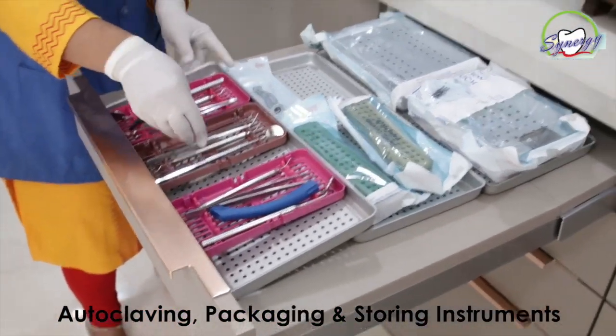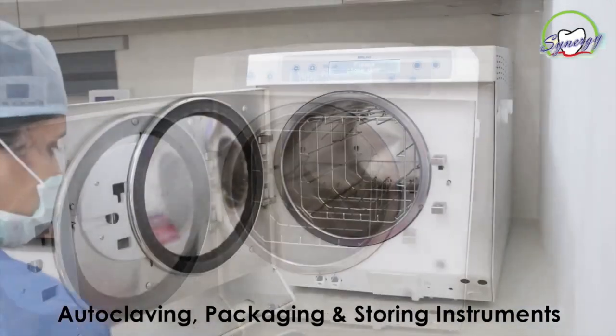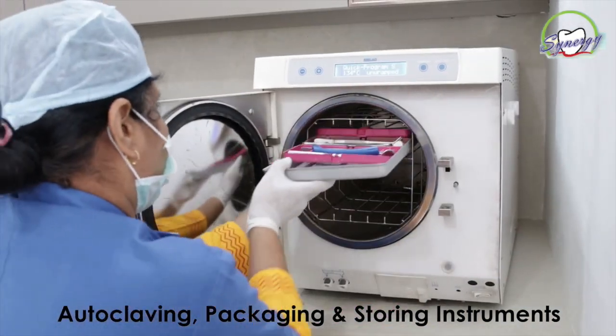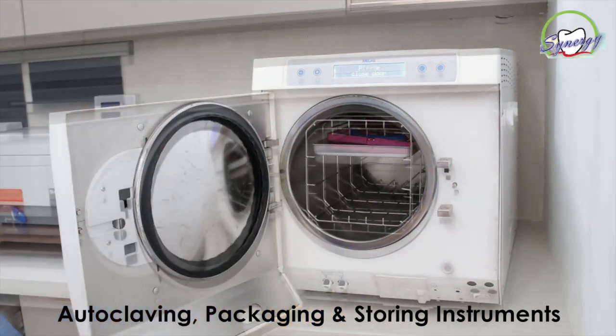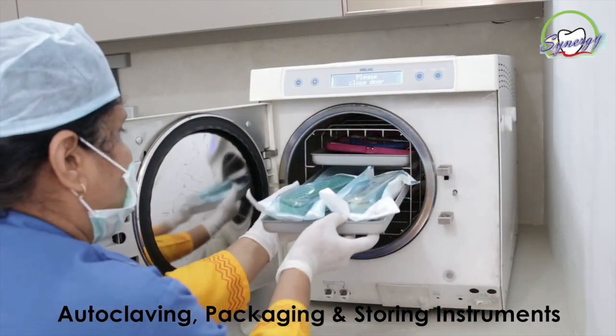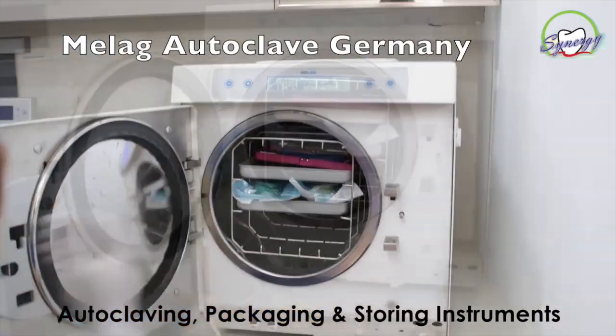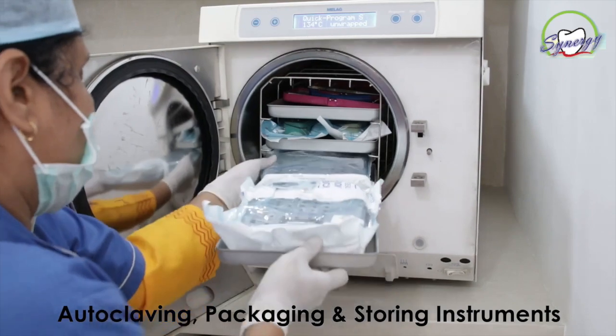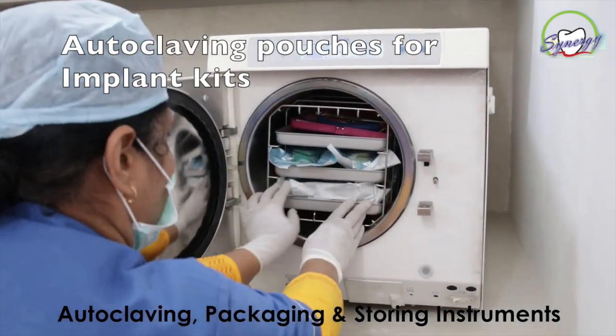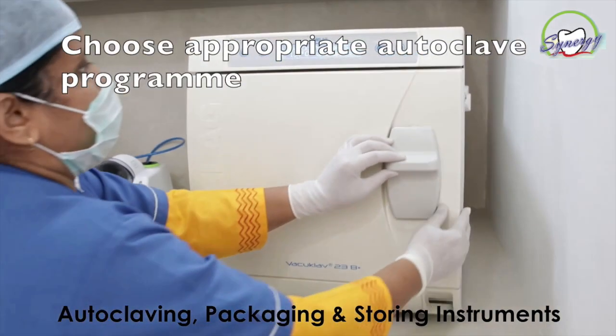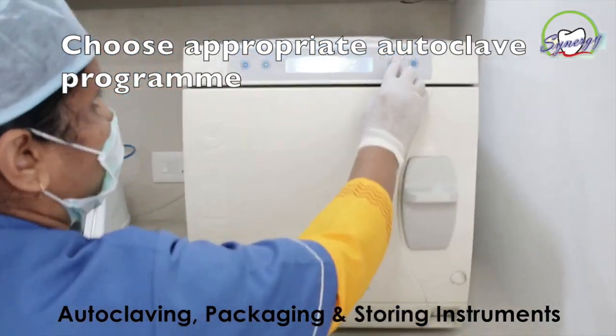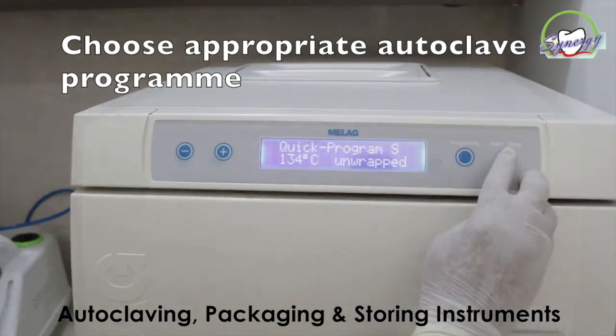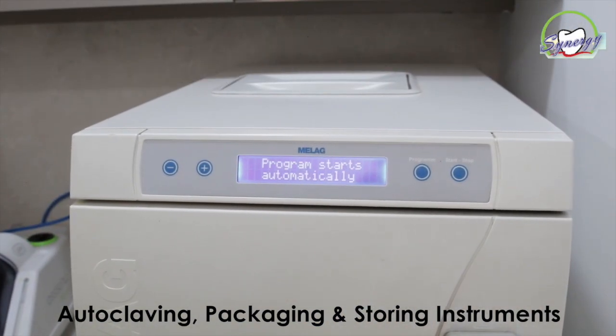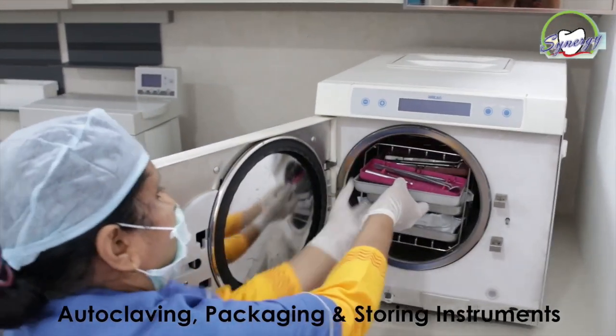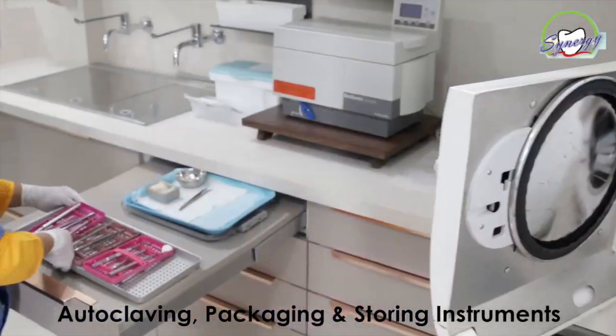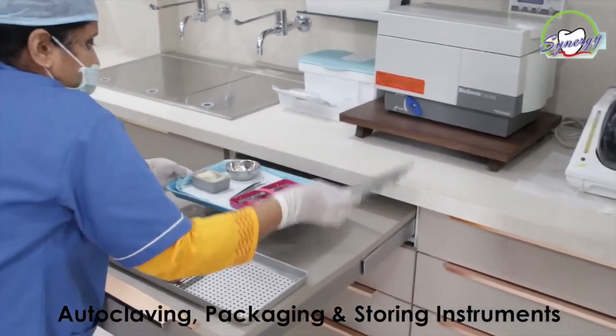The instruments are then sterilized in an autoclave, which is the Melag Class B autoclave from Germany. The use of a Class B autoclave is ideal as it has a pre- and post-sterilization vacuum, and it can be used for hollow instruments such as handpieces and implant drills. After sterilization, the instruments are removed and placed in a clean area. We store them in the overhead storage of our sterilization center.